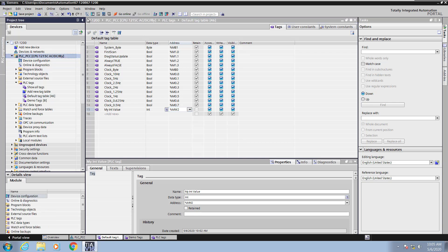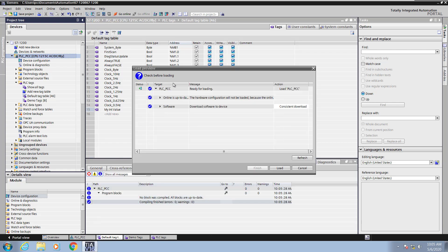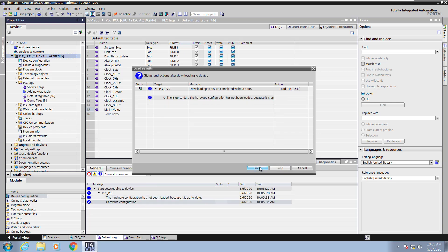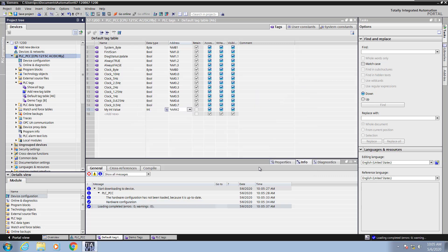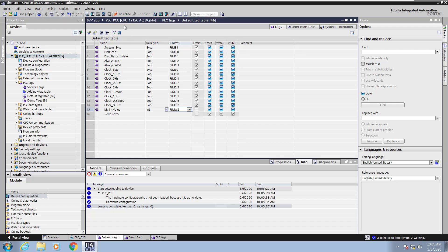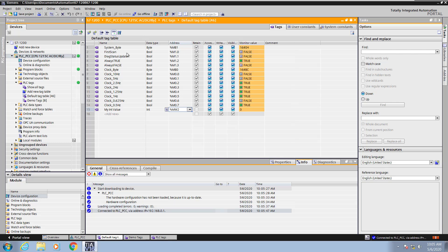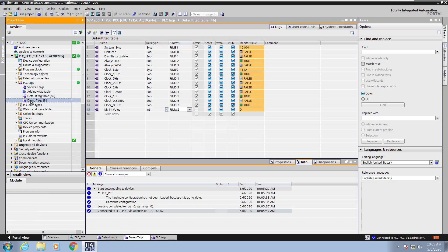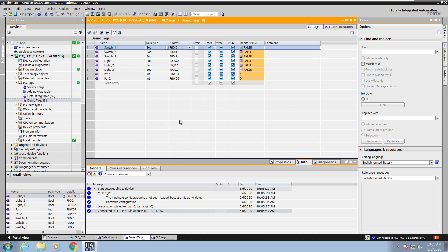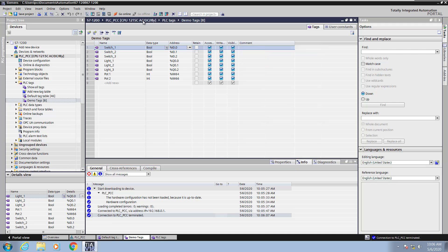Next I'm going to highlight my PLC and download the changes into the PLC. I will select load and hit finish. There's a nice feature where you can open up a tag table — my default tag table is open and I'm going to select monitor. When I select monitor this will put me online with the PLC and now I can monitor the values of the tags. You can see the values changing in the monitor value. If I open up the demo tags table and select monitor you can see the values there as well. If I flip switch1 you can see the monitor value go true; switch it back and it goes false. Now I'm going to select go offline, and this concludes the lesson on creating PLC tags.